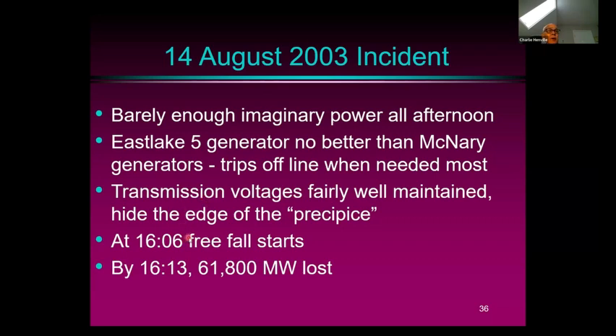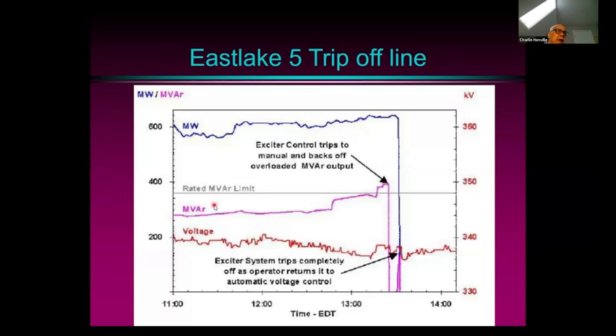So at 6 minutes after 4, the blackout started, and by 13 minutes after 4, the 61,000, nearly 62,000 megawatts of load had been lost. And here we see the reactive power output at East Lake Power Station, and we see from all afternoon, from 11 a.m. until 1 or 1:30 p.m., the voltage was being maintained okay, but the reactive power of these generators was being stretched to its limit. And this is what I said, these generators were no better than the McNary generators. They tripped offline when they were needed most. The operators tried to put it back online, but it was not successful, and the blackout ensued.